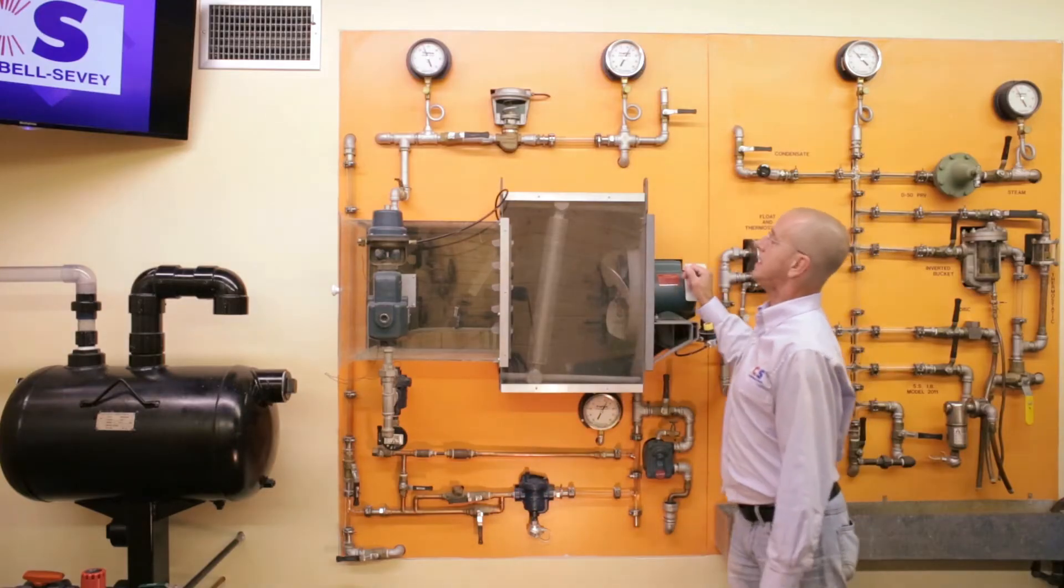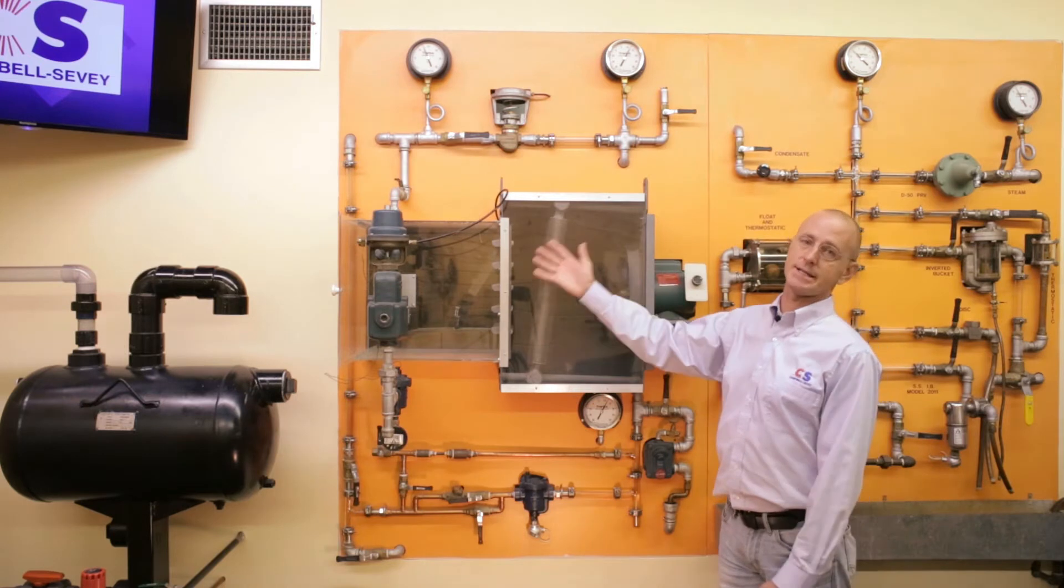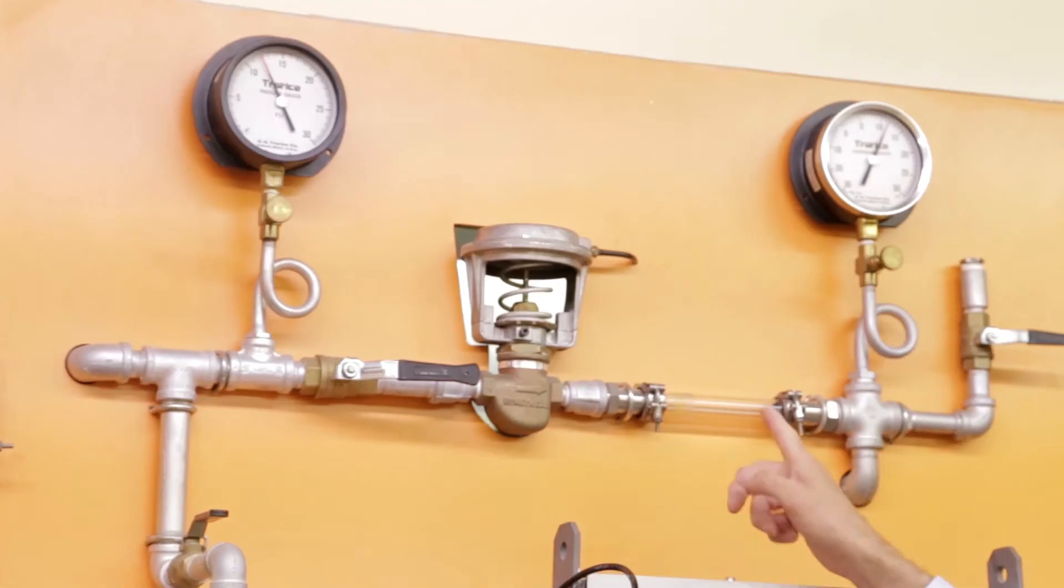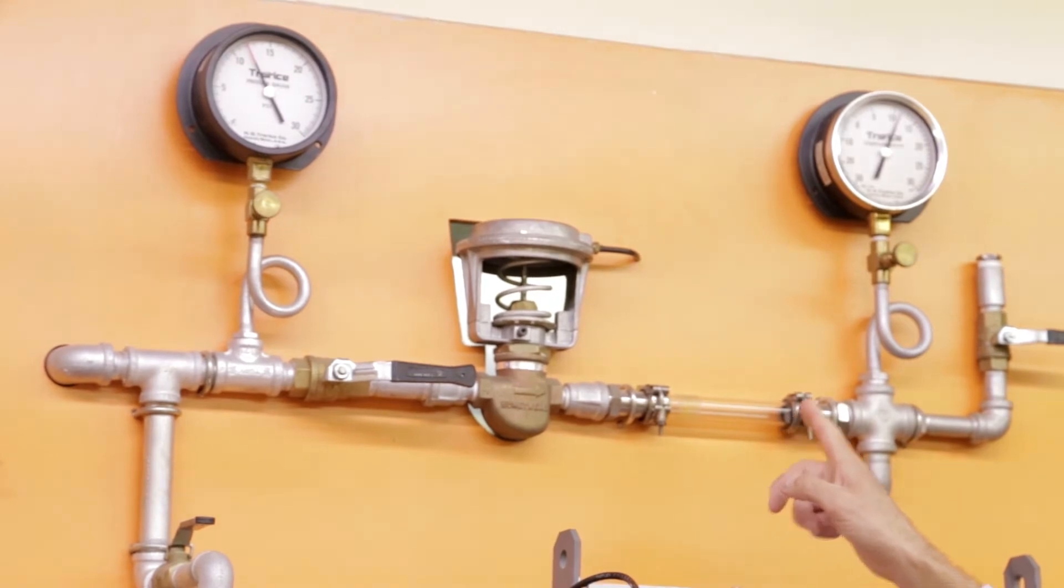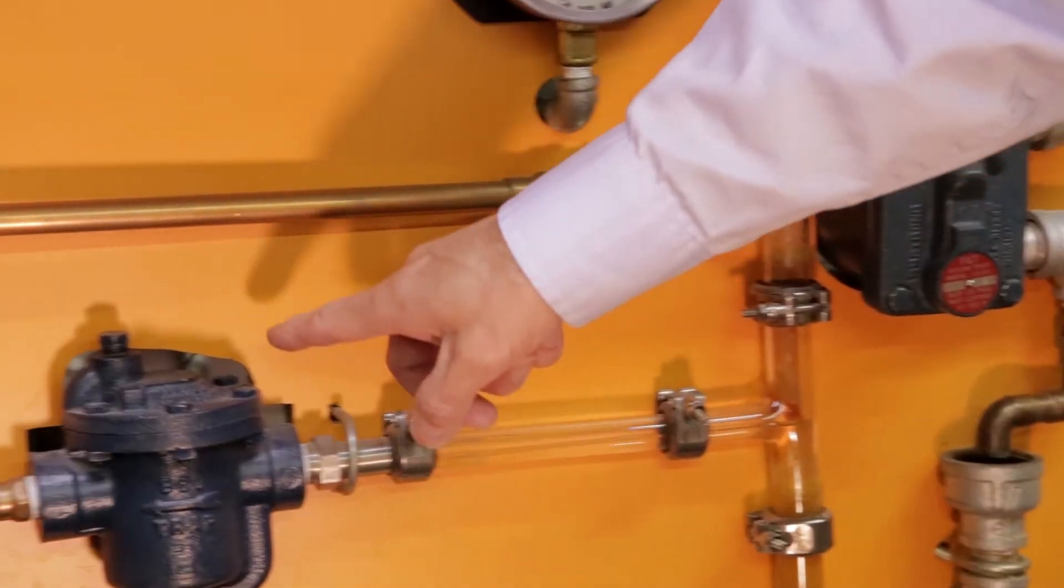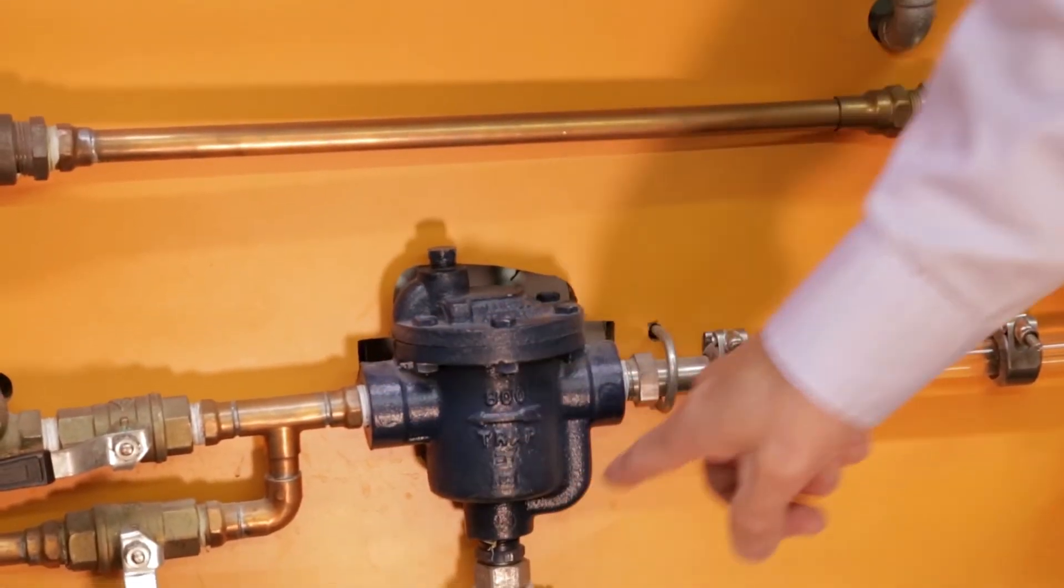So if we turn the fan on, this is how the coil would operate on design day. We've got our control valve wide open. We've got a little bit of differential pressure across the control valve, but mostly we've got plenty of differential pressure down here to push condensate through our primary trap, and everything works just fine.